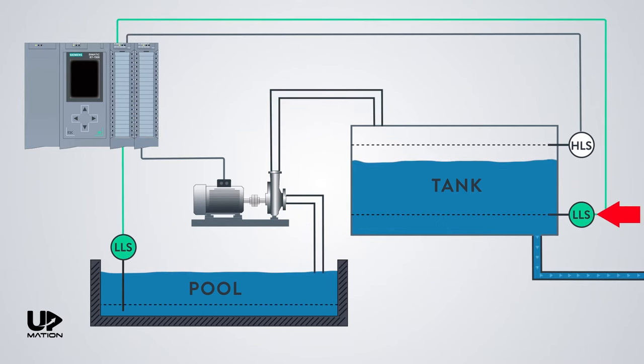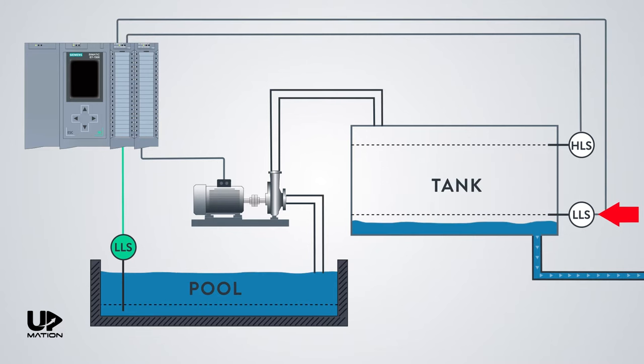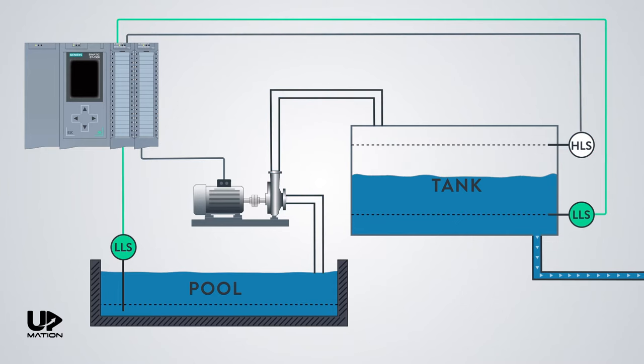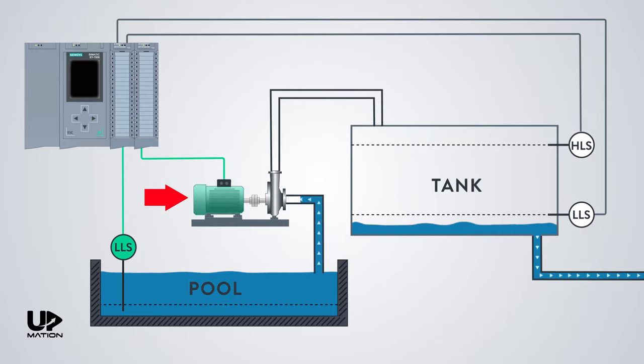As soon as the low-level switch on the tank does not sense the water, PLC should send the start command to the pump, and the pump will start working until the high-level switch senses the water. When the high-level switch senses the water, the PLC will send the stop command to the pump, and the pump will shut down and remain shut down until the low-level switch of the tank does not sense the water again. This procedure will be repeated again and again.